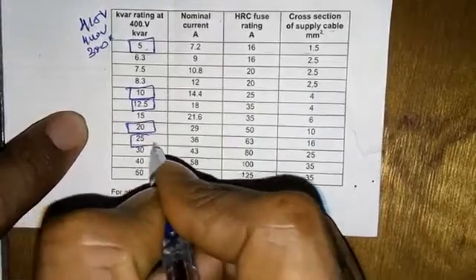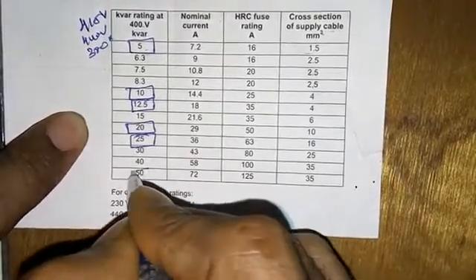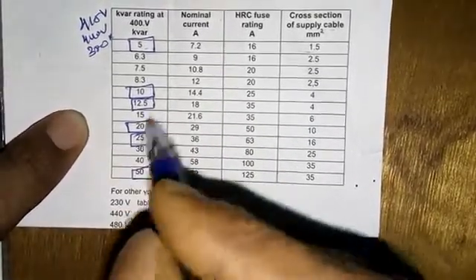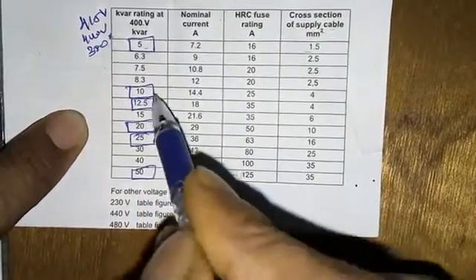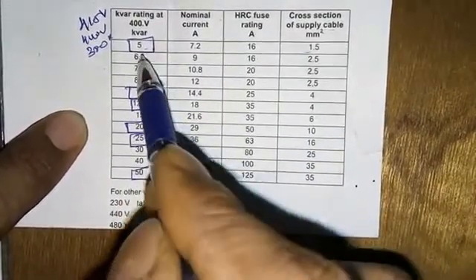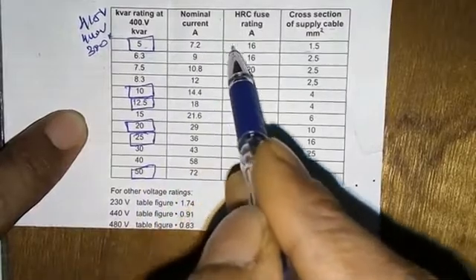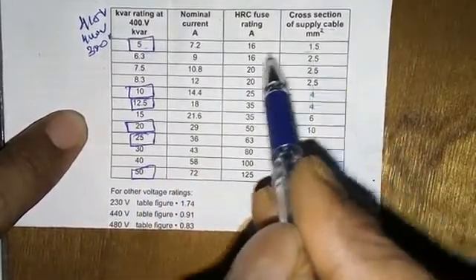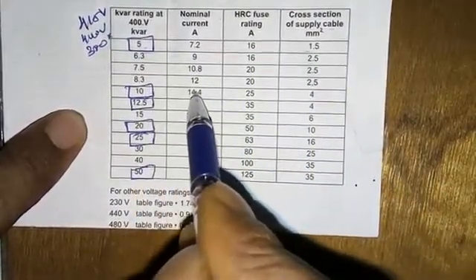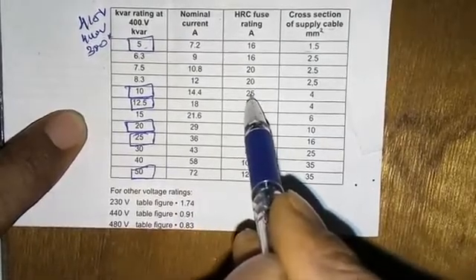Some popular capacitors we can use in the assembling are 5 kVAR, 10 kVAR, 12.5, 20, 25, and 50. These are the capacitors we always use for capacitor bank making. The 5 kVAR is 7.2 ampere with 16 ampere HRC fuse, and 10 kVAR is 14.4 ampere with 25 ampere HRC fuse for 4 square mm wire.